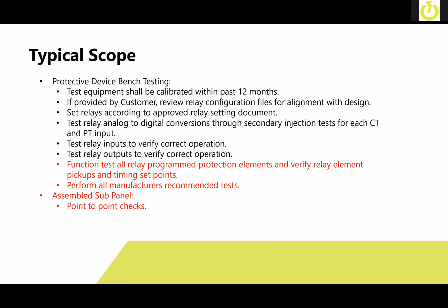Relay analog to digital conversion through secondary injection tests for each CT and PT input. And we test relay inputs and outputs to verify correct operation. We also recommend that you function test the relay program protection elements and verify the element pickups and timing set points. That ensures that it's set in accordance with the system design. And also perform all manufacturer recommended tests.